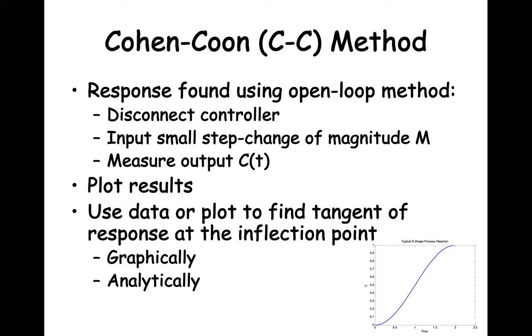If we plan to use the Cohen-Coon method to collect information to find the values of Kp, tau i, and tau d, we need to disconnect the controller. This means there will not be any processing adjustment made when there is a change to one of the inputs. With the controller disconnected, we will make a small step change of magnitude M to one of the inputs. Then we measure the process output C(t) and plot the results. Hopefully you will get the S-shaped response shown in the previous slide, and we will use the output information to find values to calculate recommended values for Kp, tau i, and tau d.